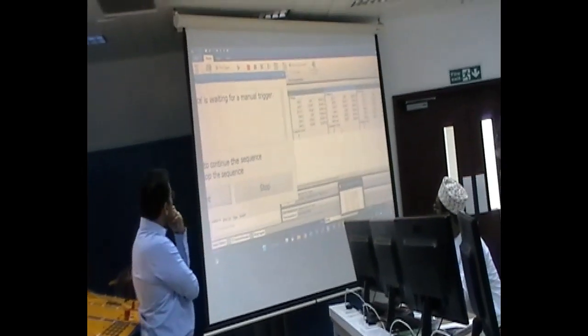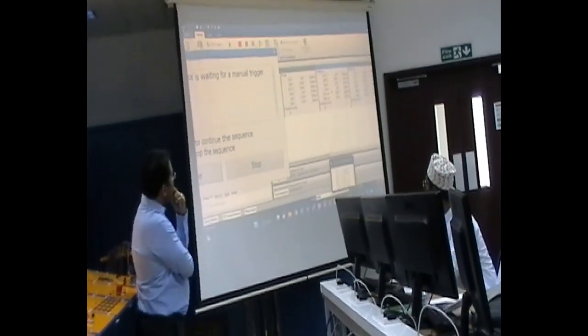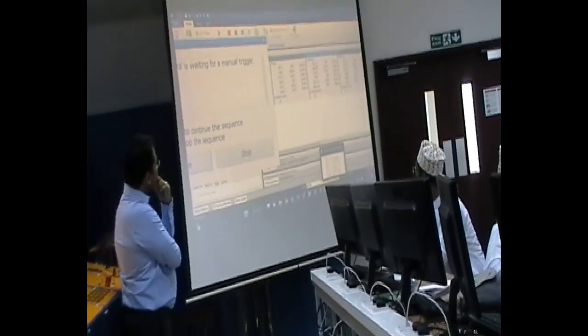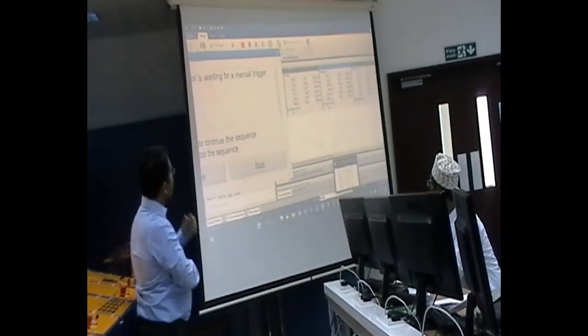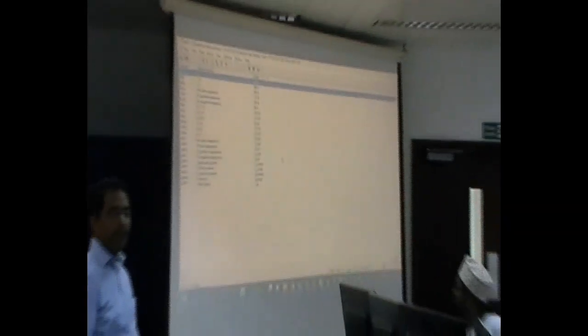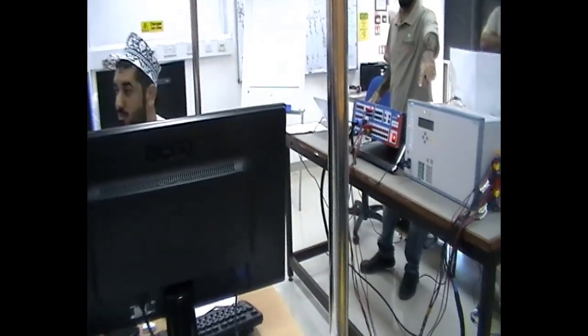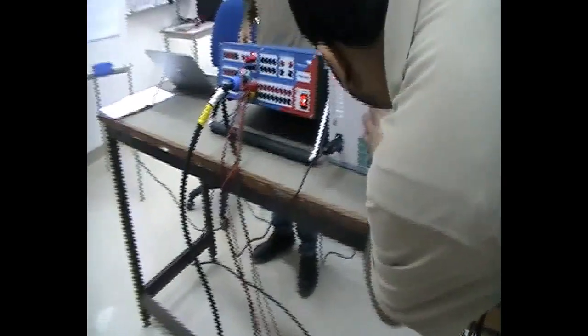Now I'm showing you in the Omicron whatever I have injected. I've injected 63.5 volts in the red, 40 volts in the yellow phase, and 20 volts in the blue phase. Now I want to check the relay. I could be looking at the screen here and reading from it, or because I have already communicated with the relay and I have online communication, whatever appears here is from the relay. You can also connect through USB to the relay if you would like.